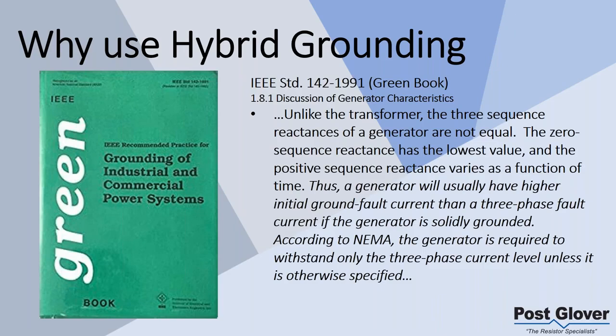The reason is that at the end of the day, you have a potential for a ground fault being higher than the three-phase short circuit current that the generator is braced for. That's based on the variation of positive sequence reactances versus zero sequence reactances. We don't need to get into those details, but the bottom line is you need to be braced correctly. Medium voltage generators are not necessarily going to be braced correctly on a solid ground system. Therefore, IEEE recommends users use a resistor. So we start off at that point.